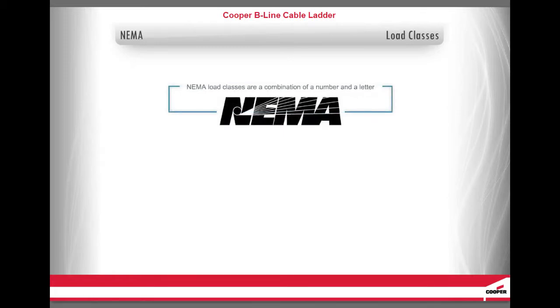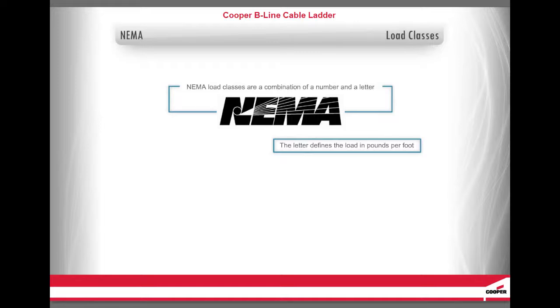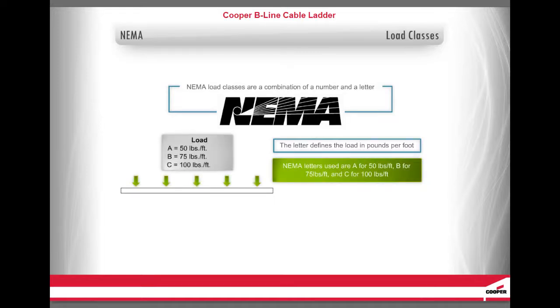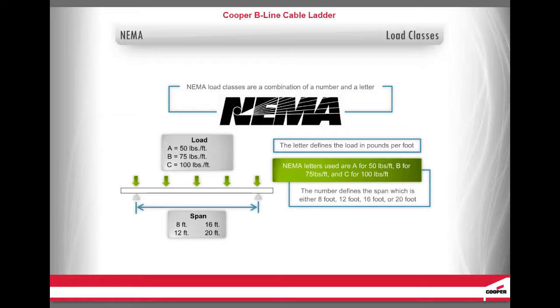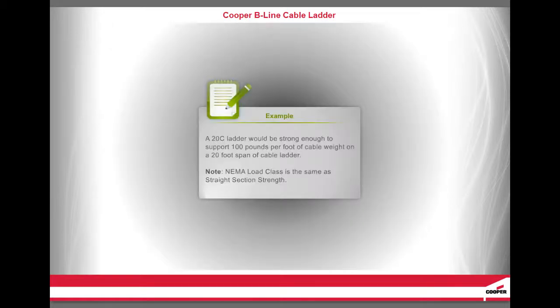NEMA load classes are a combination of a number and a letter. The letter defines the load in pounds per foot. The NEMA letters used are A for 50 pounds per foot, B for 75 pounds per foot, and C for 100 pounds per foot. The number defines the span. NEMA span is either 8 foot, 12 foot, 16 foot, or 20 foot. A 20C ladder would be strong enough to support 100 pounds per foot of cable weight on a 20-foot span of cable ladder. Note: NEMA load class is the same as straight section strength.